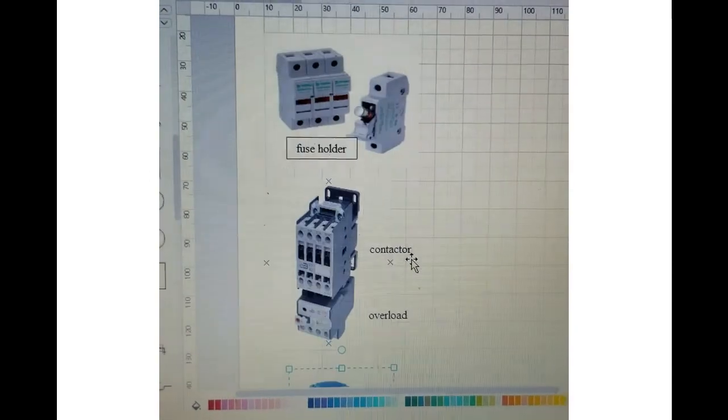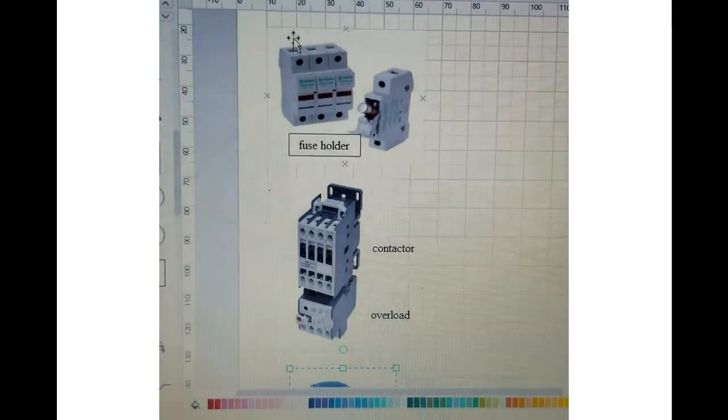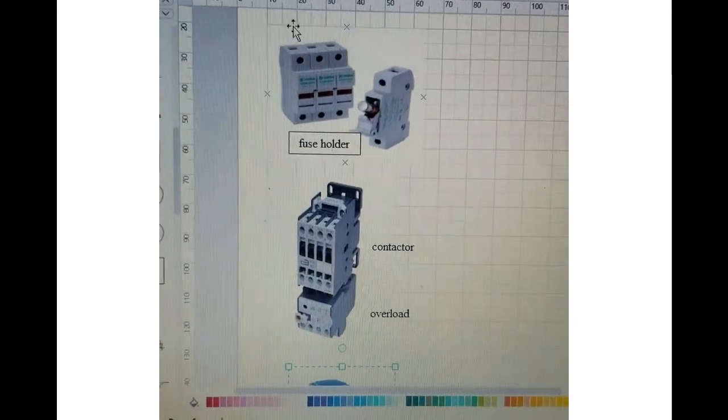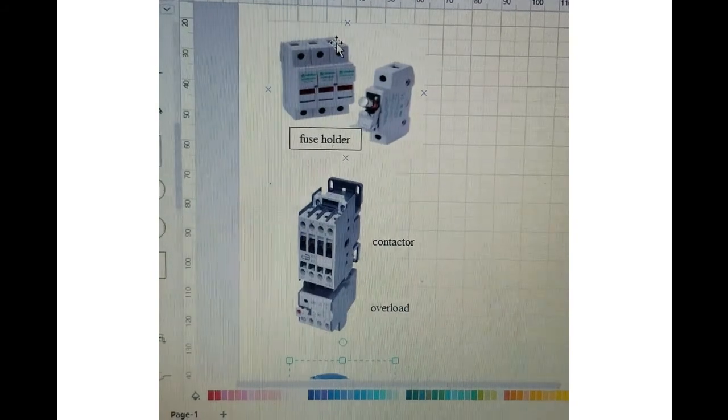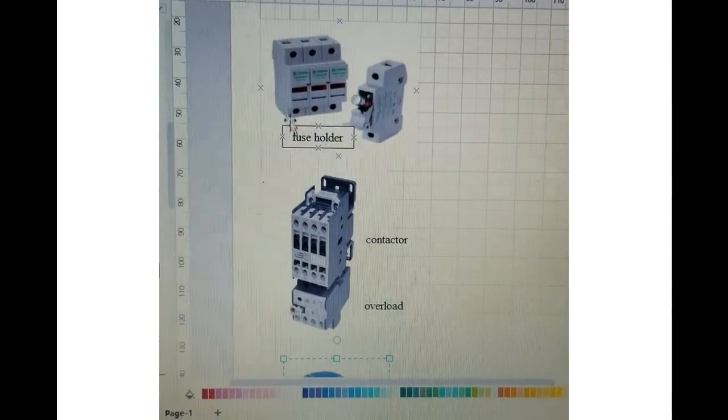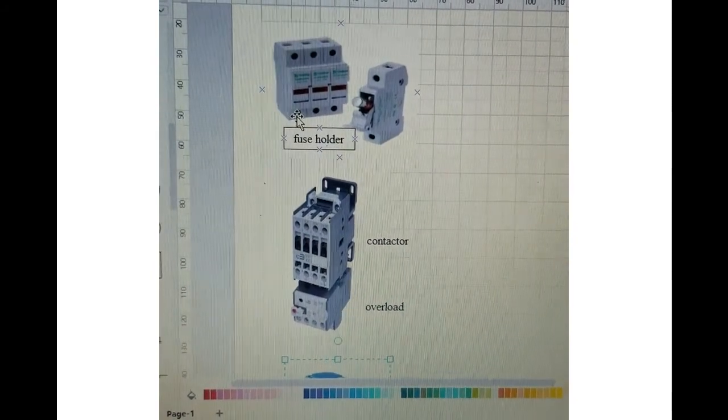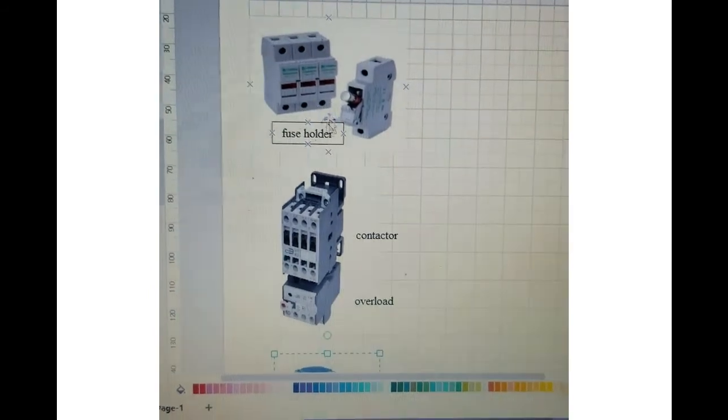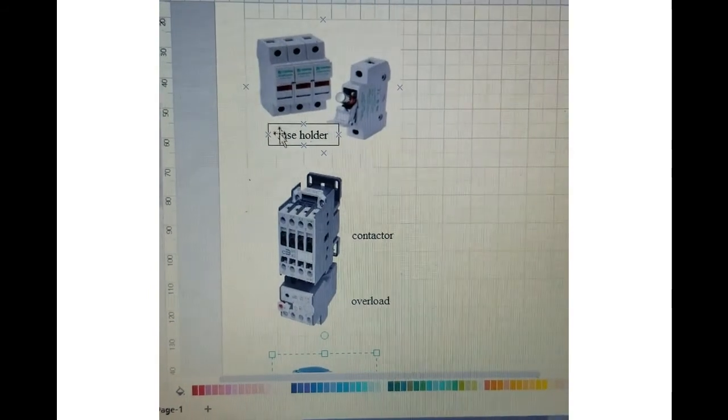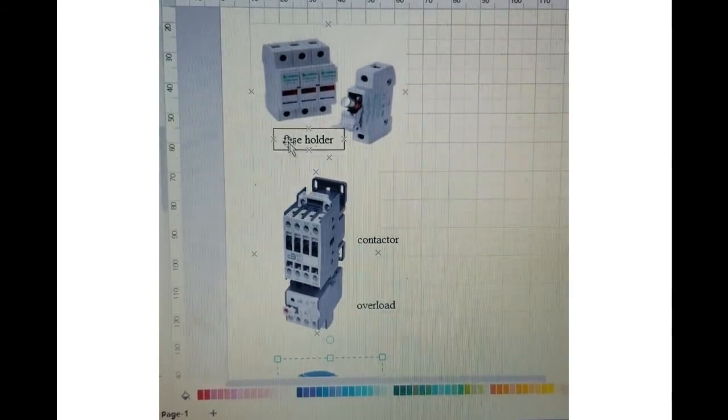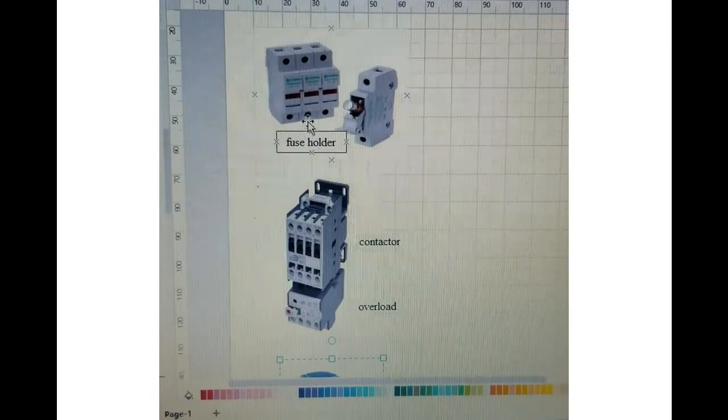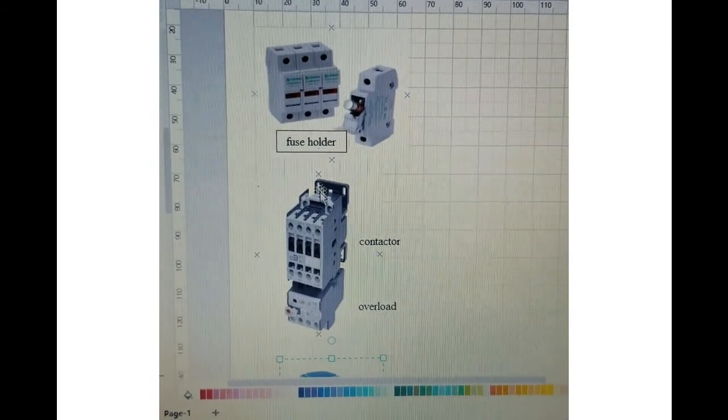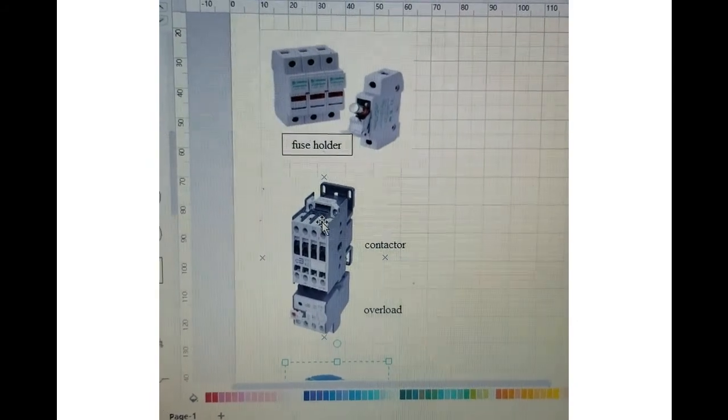Basically how it's going to work is this: our three phases L1, L2, L3 will come on top of this fuse holder, then they're going to come out from the bottom of the fuse holder and they will go to the top of the contactor - from here to this point, second one to this point, and L3 to the third point on the contactor.